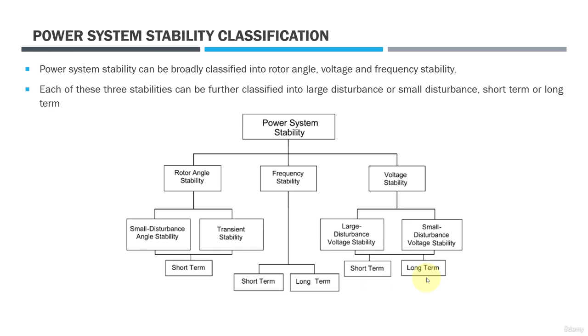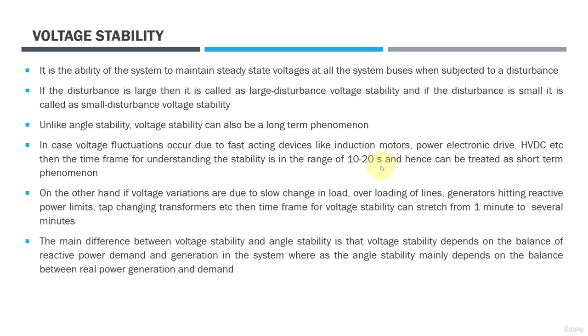In case voltage fluctuations occur due to fast-acting devices like induction motors, power electronics drive, HVDC, etc., then the time frame for understanding the stability is in the range of 10 to 20 seconds, and hence voltage stability can be treated as a short-term phenomenon. On the other hand, if voltage variations are due to slow change in load, overloading of lines, generators hitting reactive power limits, tap changing transformers, etc., then the time frame for voltage stability can stretch from 1 minute to several minutes.